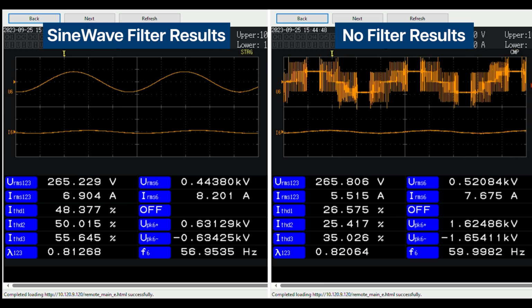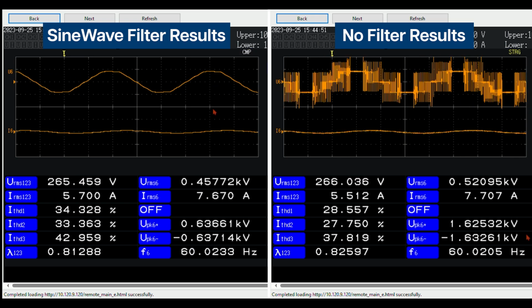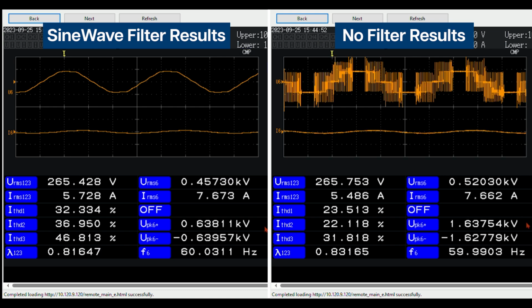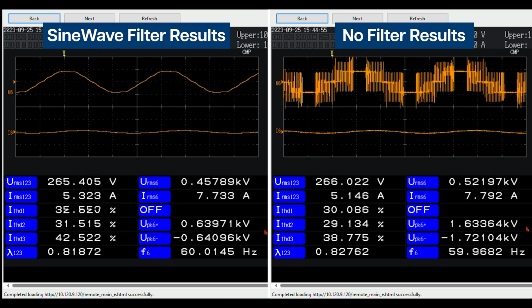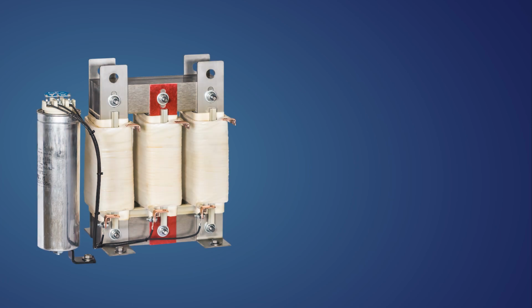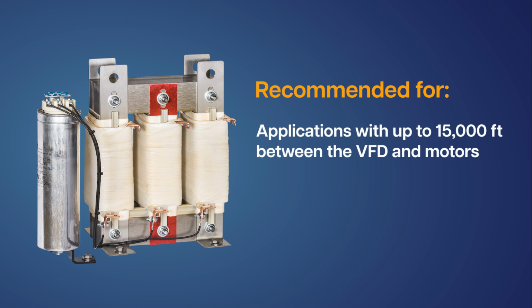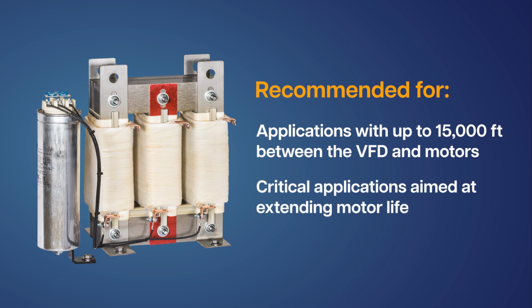It also strategically positions the resonance frequency peak away from operating and switching frequencies to protect the motor from potential harm. The sine wave filter is particularly recommended for scenarios with cable runs up to 15,000 feet between the VFD and motors, as well as in critical applications aimed at extending motor life and reducing downtime risks.